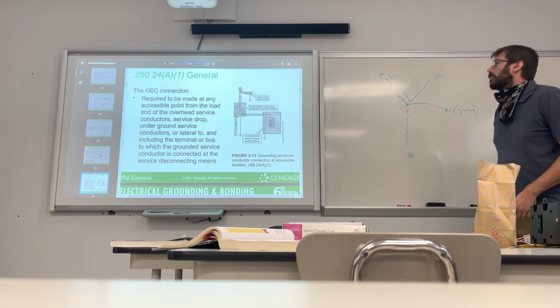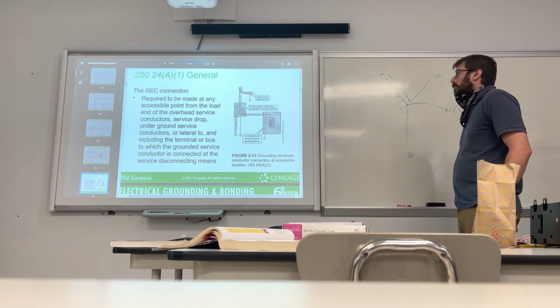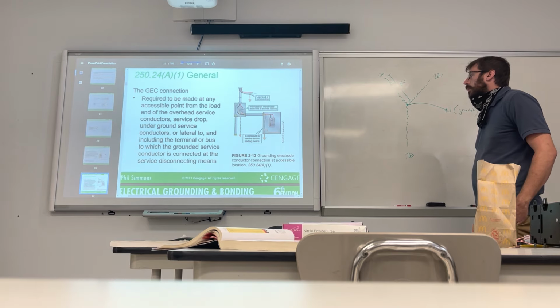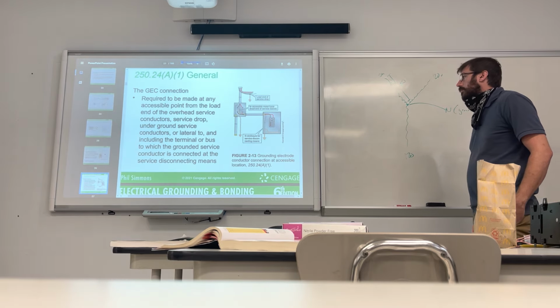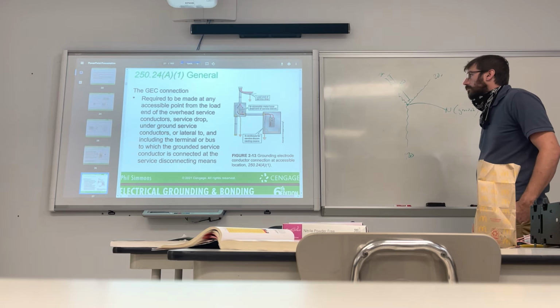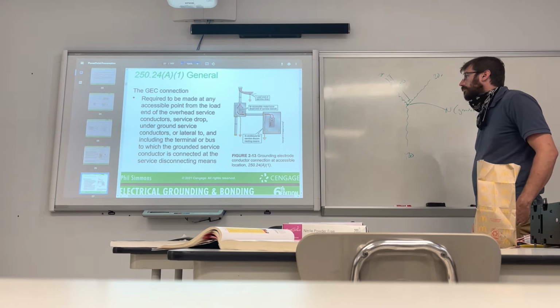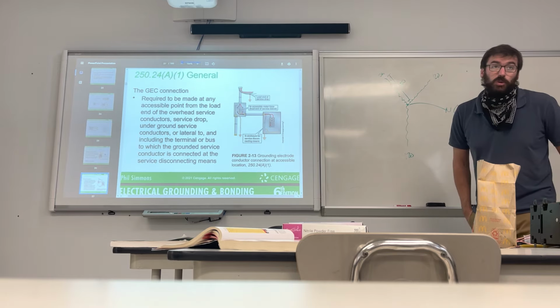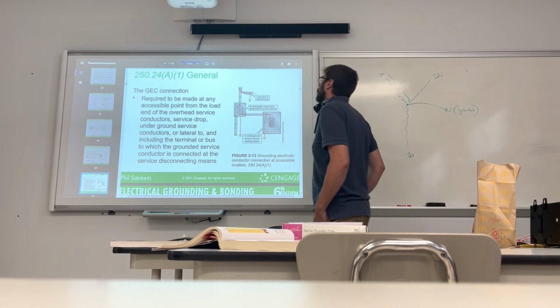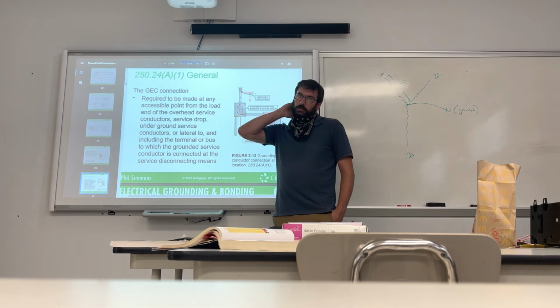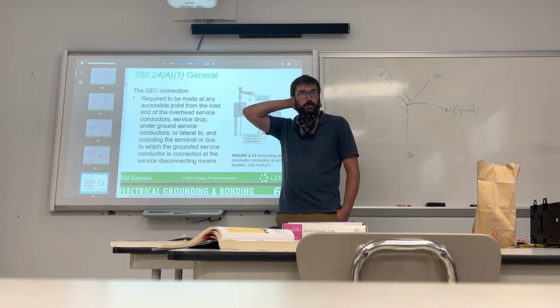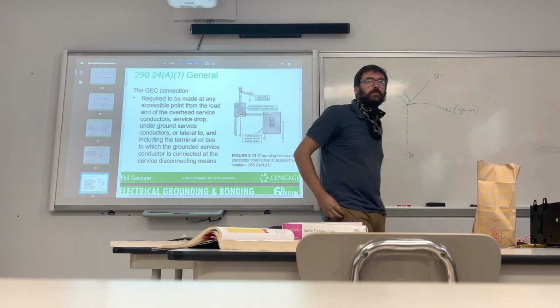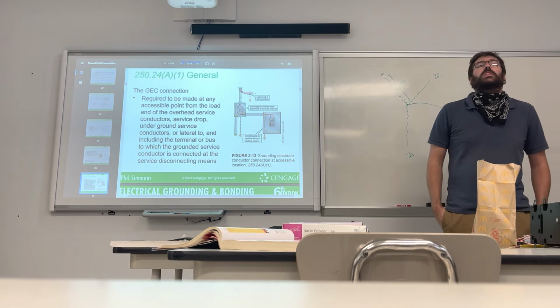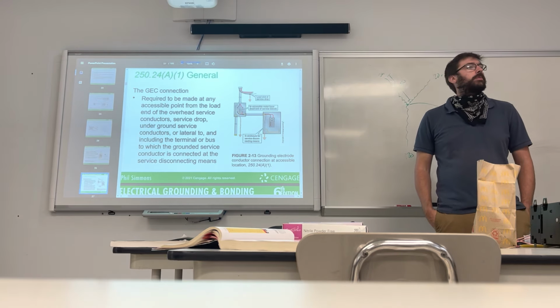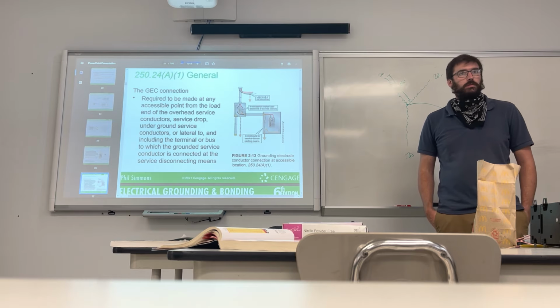The GEC connection is required to be made at any accessible point from the load end of the overhead service conductors, service drop, underground service conductors, or lateral to, and including the terminal or bus to which the grounded service conductor is connected at the service disconnecting means. This is a loaded question. Let me ask you a question. Is this meter base accessible for inspection? Think long and hard about that. Is the meter base accessible for inspection?